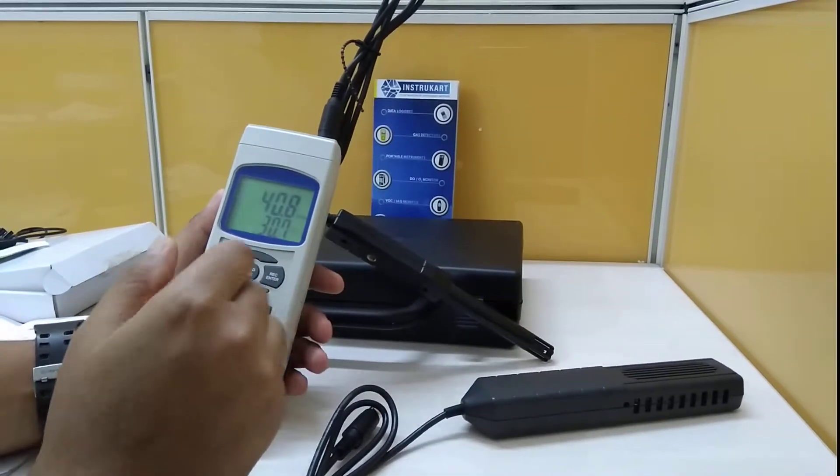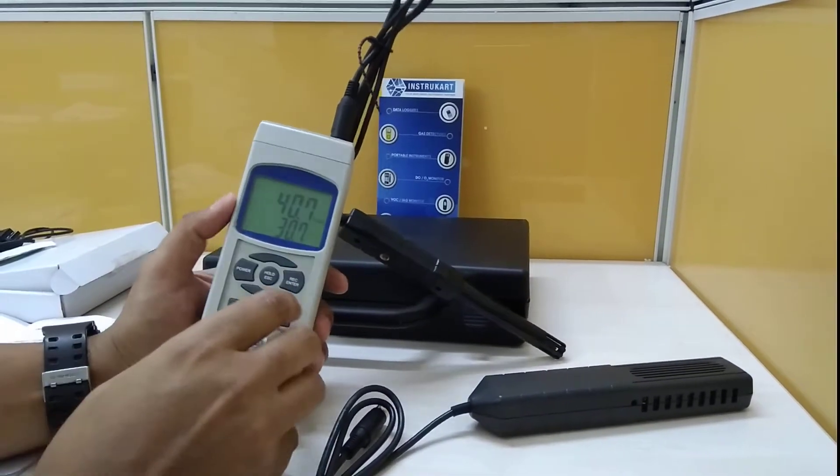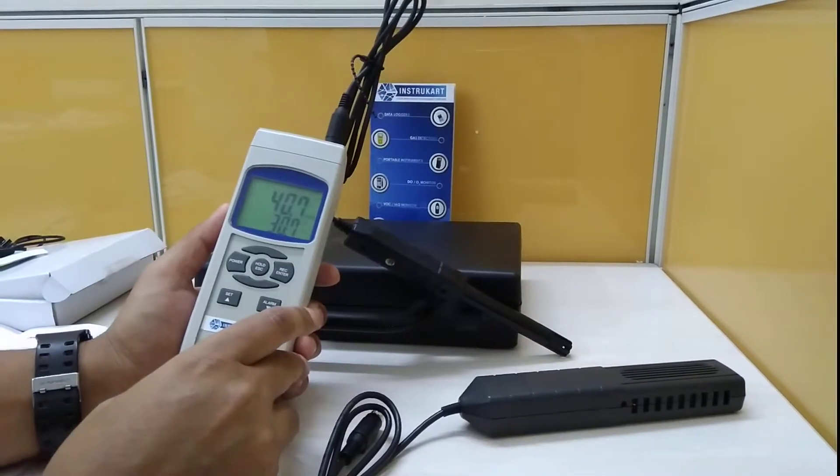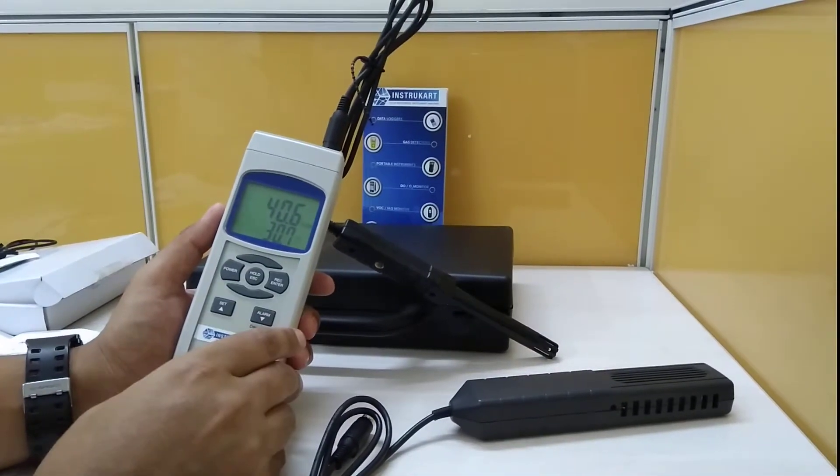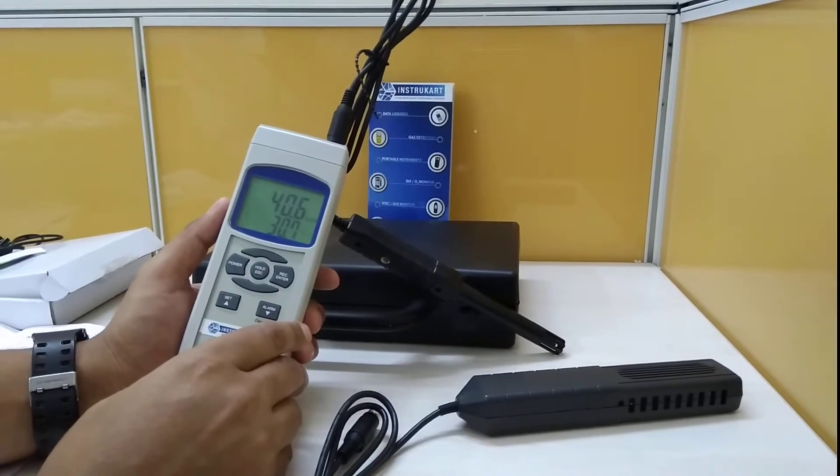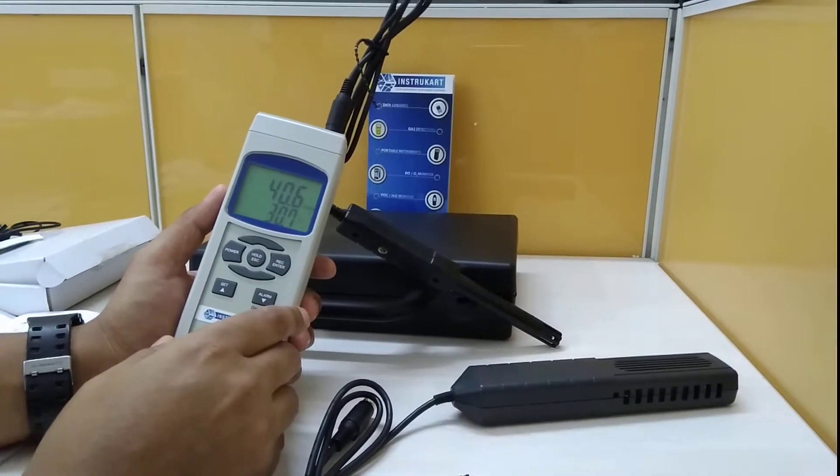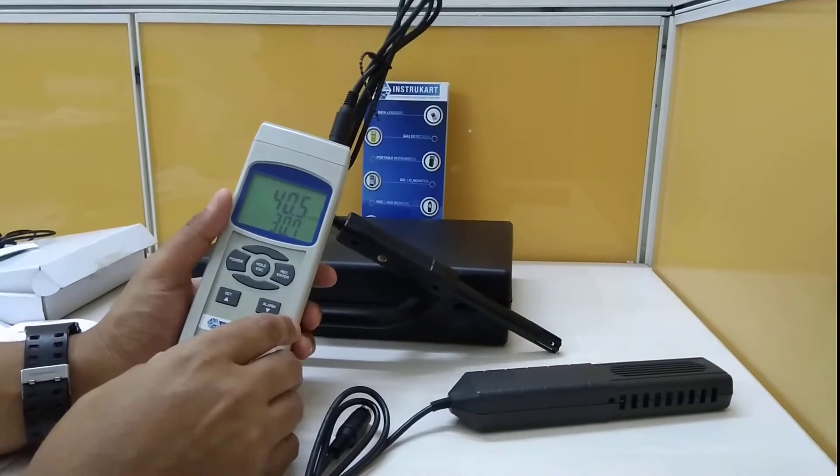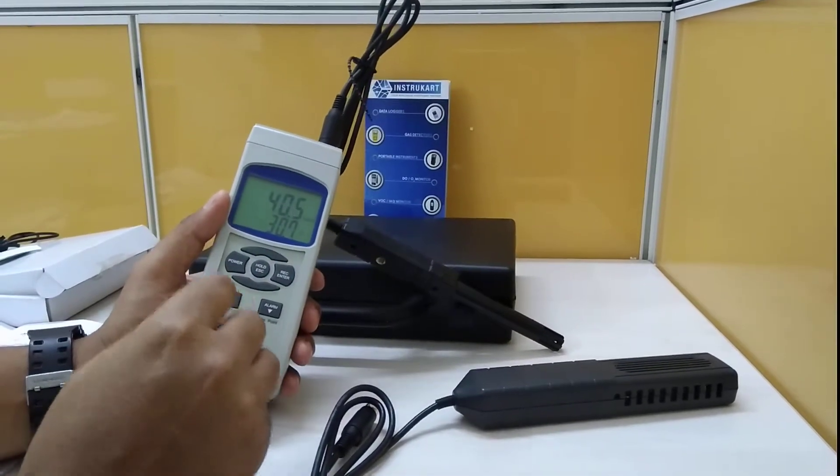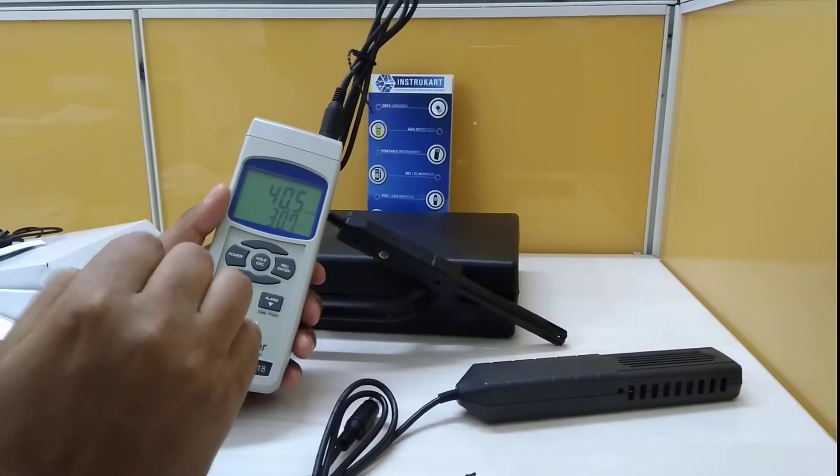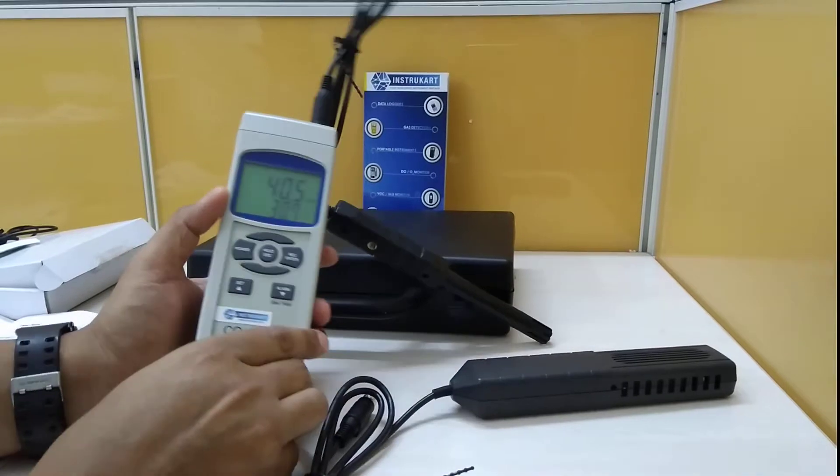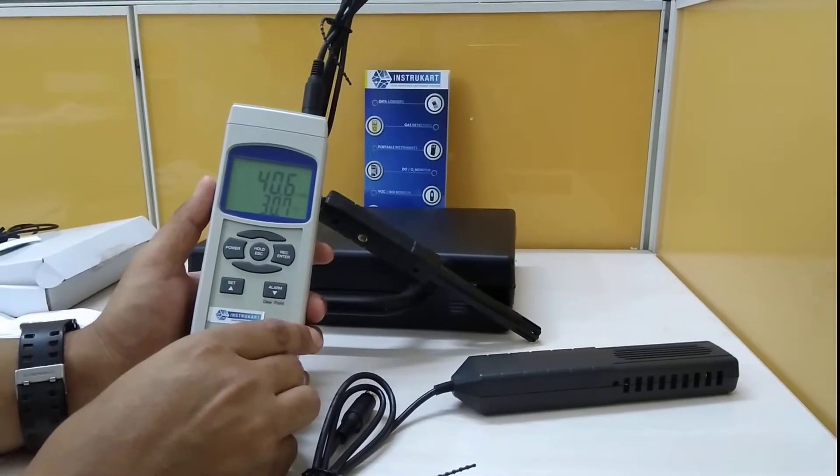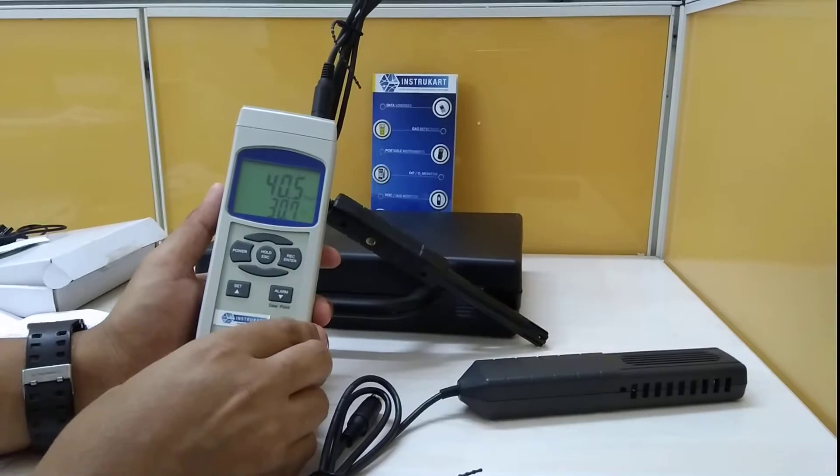First, the temperature and humidity. The temperature range is 0 to 50 degrees Celsius with a resolution of 0.1 degrees Celsius and accuracy of plus or minus 0.8 degrees Celsius. The humidity range is 10 to 95 percent RH with 0.1 percent RH resolution and 3 percent accuracy of the reading when greater than or equal to 70 percent RH.